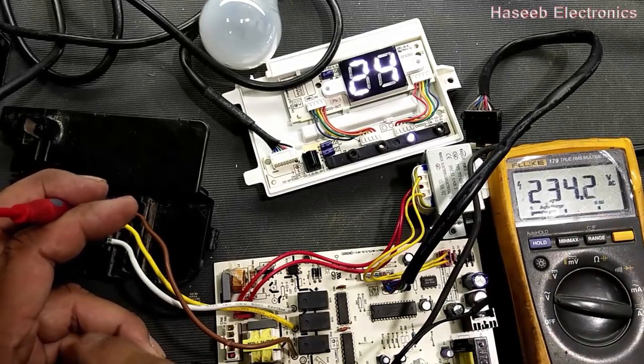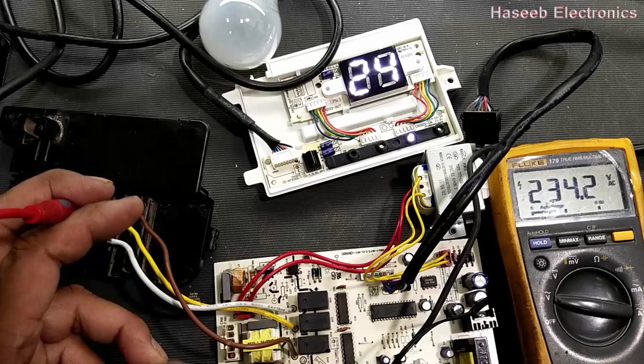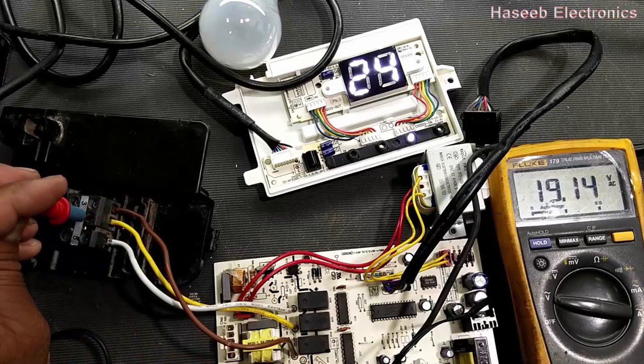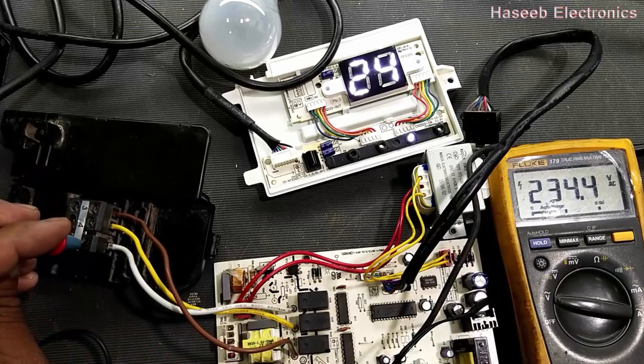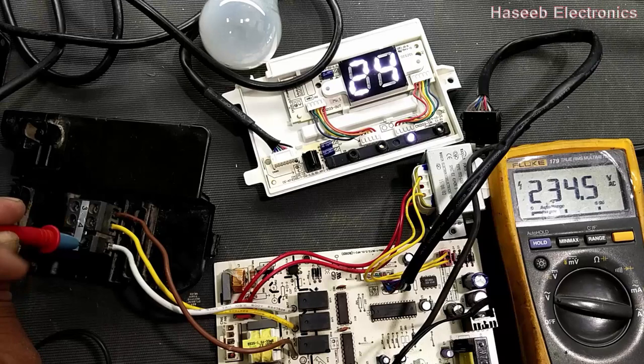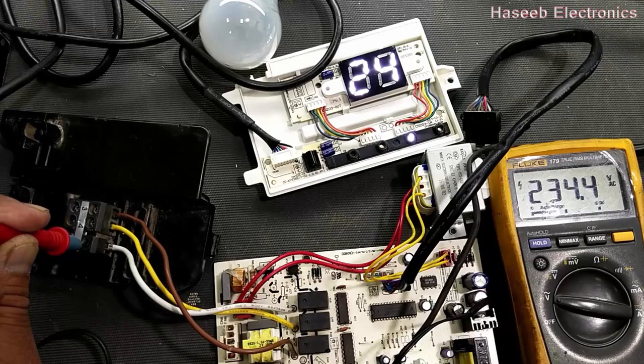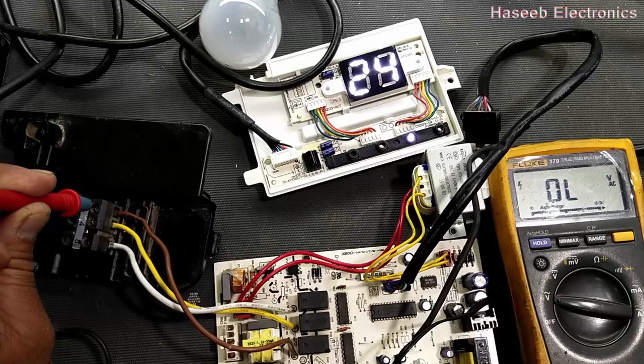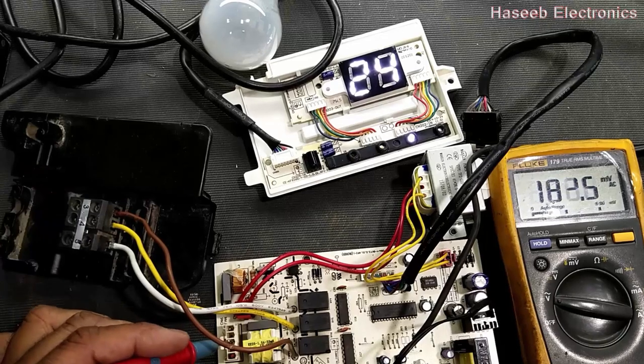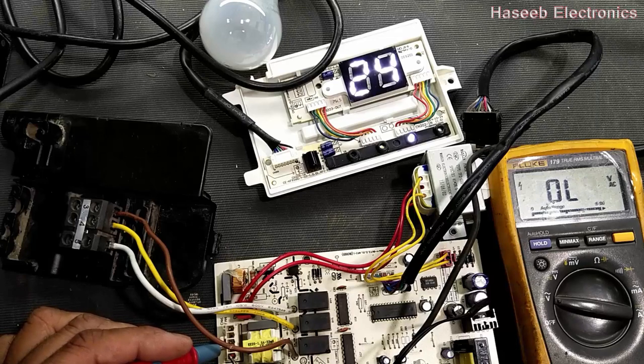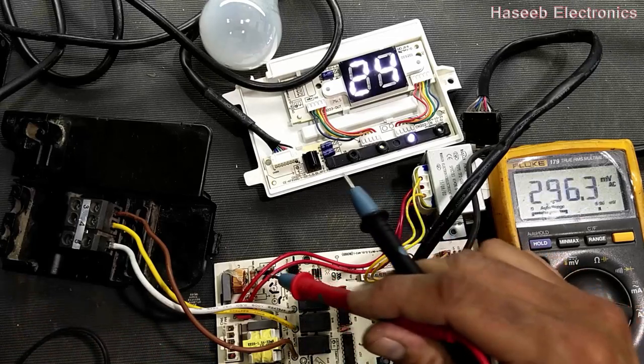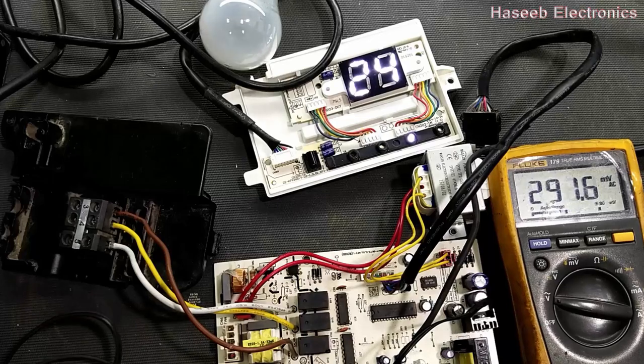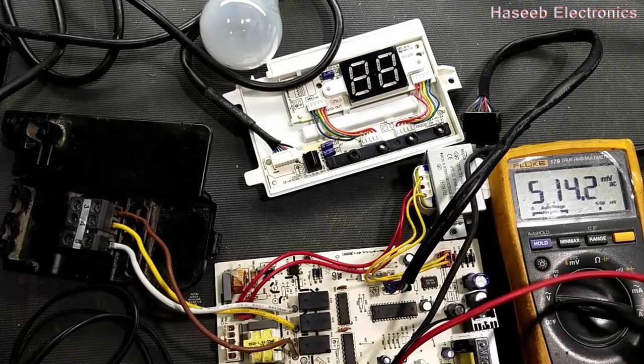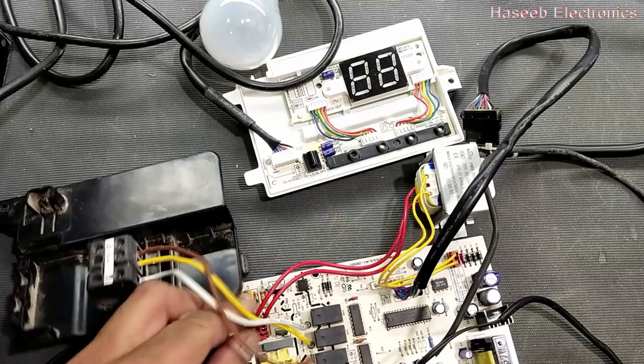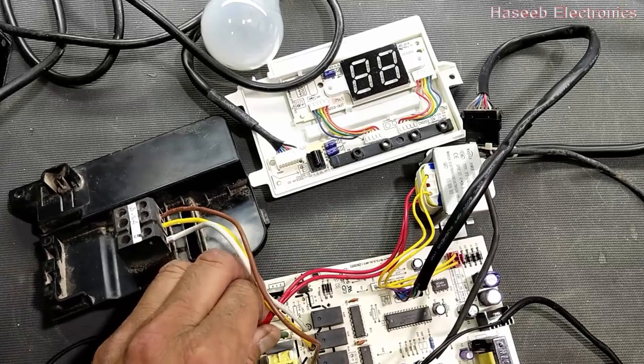So now this board started output voltage, and we have fan voltage and we have compressor voltage. For the indoor fan motor we don't have voltage because this triac's one leg is broken, so we have to connect it. One terminal is broken.